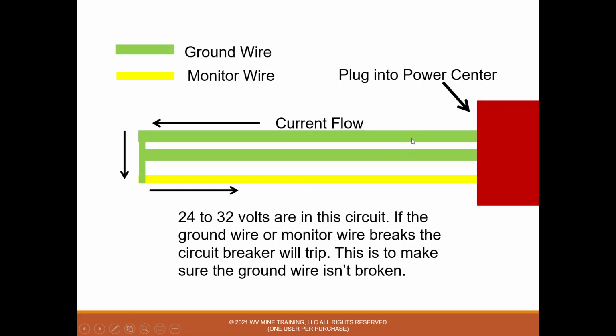So again, we have electrical flow through the ground wire to the monitor. This is a complete circuit, and this circuit holds the breaker in. And we have energized equipment. We can work, we can mine, we can roof bolt or whatever. But if the ground wire would get broke or the monitor wire would get broke, then the holding circuit would drop out and the breaker would kick. Very good safety device. Make sure you always have a ground.